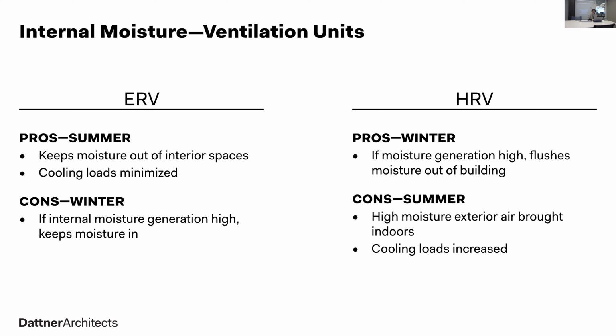So the engineers at Dagger did an analysis of the humidity in the building. And since our ERVs serve around 70 apartments each, what they found through that analysis is that the high relative humidity conditions in some apartments in the winter would be mitigated by the other apartments. All that air is mixing together in the ERV. And when the fresh air is brought in, the high humidity apartments are going to get lower humidity air. We do have humidity sensors throughout the system.